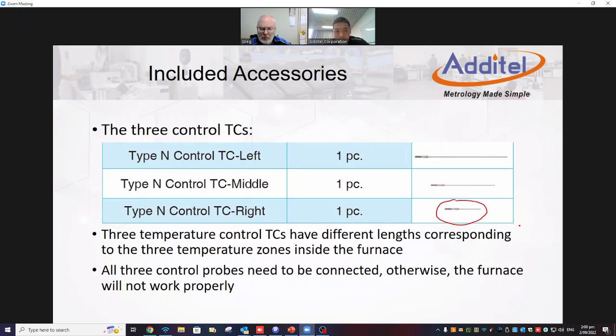If the customer wants to use their own probe as a control probe, no problem. They can use the type S or something like that as the control probe. Yes. Actually, the 3 control thermocouples are connected outside of the furnace, not inside. So if they want to use their own control probes, they can just remove the probe, insert their own one, and connect it to the furnace. The connection is on the outside of the furnace, so they don't need to open the furnace.